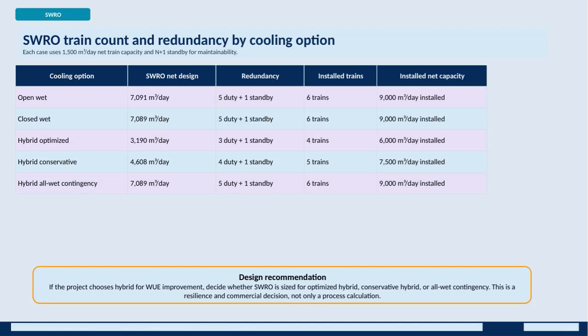Here we have the SWRO train count and redundancy by different cooling options, each based on a 1,500 cubic meters per day net train capacity, with an N+1 standby configuration to ensure maintainability. This slide summarizes a training concept package for the BADM Coastal Data Center water supply, covering SWRO desalination, direct liquid cooling, and cooling tower integration. Looking at the cooling options for both the open wet and closed wet setups, the SWRO net design capacity is around 7,090 cubic meters per day, with 5 trains operating and 1 standby, totaling 6 installed trains and 9,000 cubic meters per day of installed net capacity.